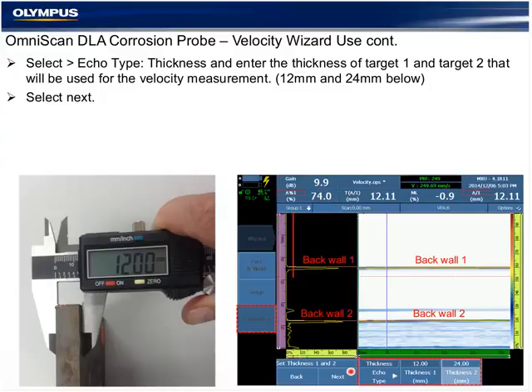And in weld inspection or corrosion mapping, what the OmniScan wizard does, like every wizard of this type, it doesn't calibrate the instrument to a velocity. That's what the old UT analog systems did. What it does is measure the velocity based on user input. And that measurement is done on one A-scan, one time, and it's completely dependent on the user taking a good measurement and the software knowing the real thickness of the component.